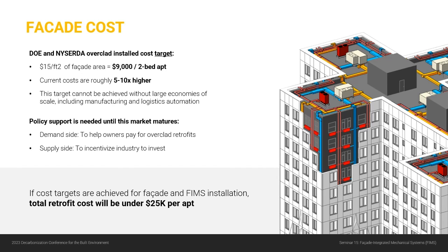So policy support needs to be a big part of that, both on the demand side, helping owners to pay for these early projects, and also on the supply side to incentivize manufacturers to really build out that capacity to be able to bring the costs down. So if we were to hit DOE and NYSERDA's target, we would be doing this complete retrofit for under $25,000 per apartment, which again, that's before incentives, and that would be incredibly attractive. But even if we look at the facade cost and say it's triple that, say it's $45 per square foot, we would still be doing these retrofits at about $50,000 total installed cost per apartment, which still works out to be quite attractive economically when you consider the benefits. And again, that's before you take incentives into account.